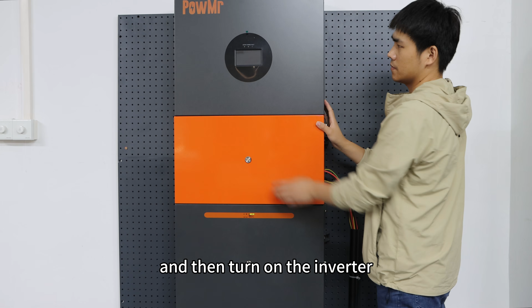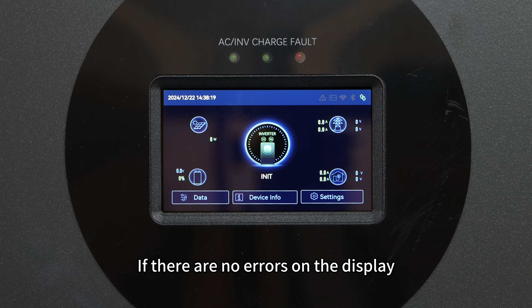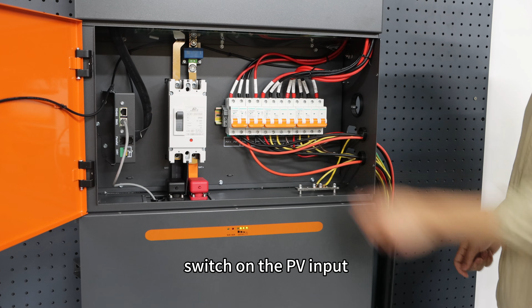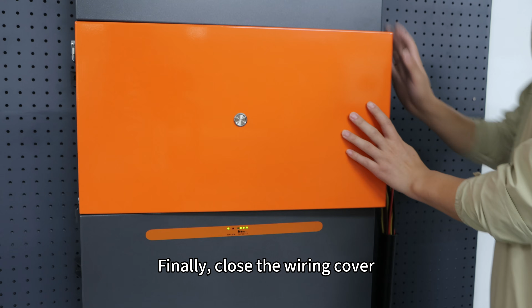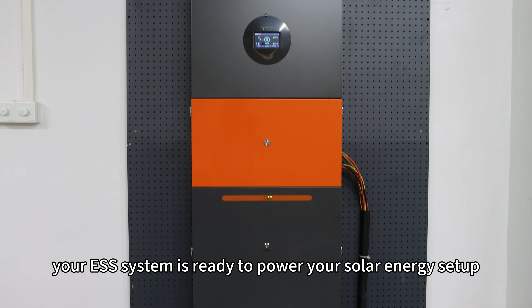Once the battery indicator shows normal operation, close the battery breaker and then turn on the inverter. If there are no errors on the display, switch on the PV inputs, grid inputs, and AC output breakers one by one. The system will then start operating normally. Finally, close the wiring cover. Now your ESS system is ready to power your solar energy setup.